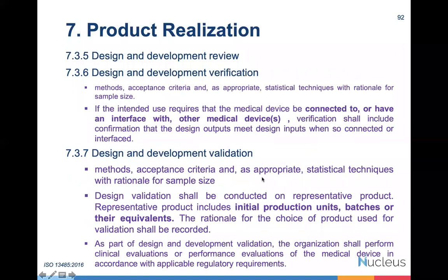The design verification and design validation. During this design verification and validation, if your product needs to be connected or it has any interaction or interface with other medical device, you need to prove that your product is verified and validated against those interfaces. That's a very critical requirement you have to consider.